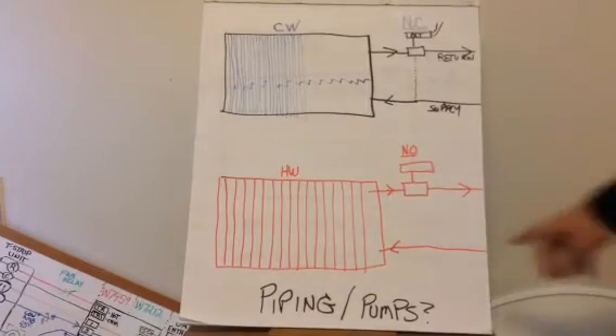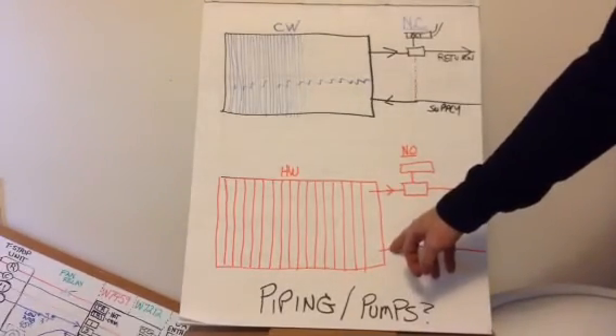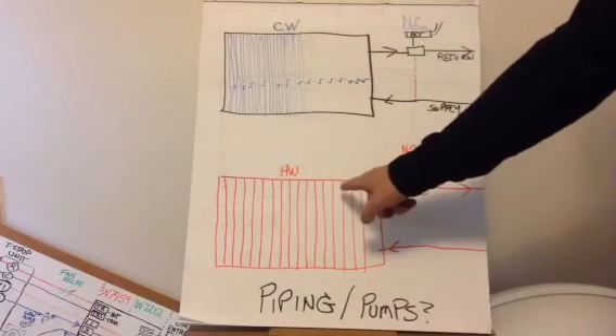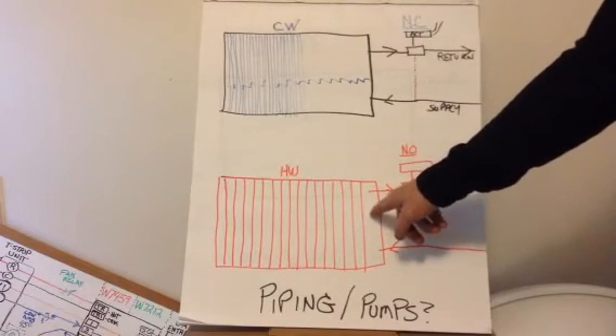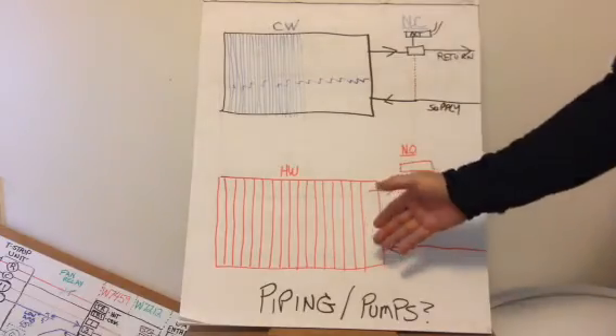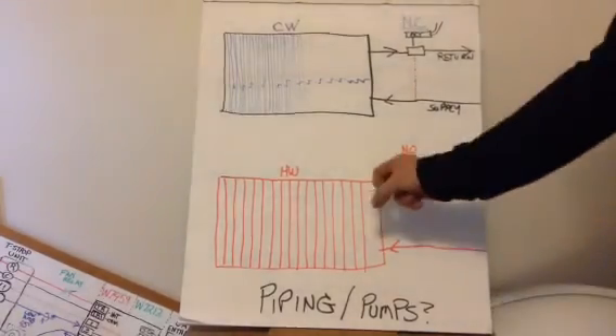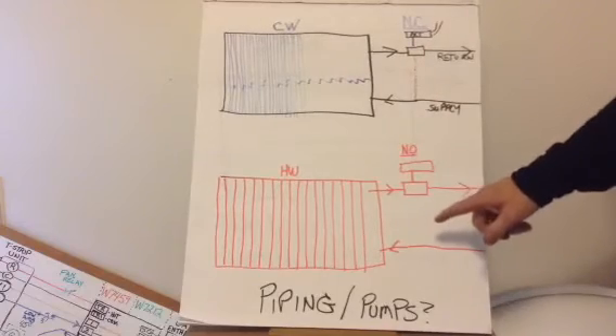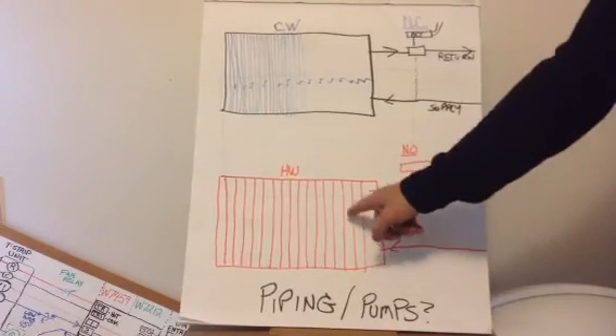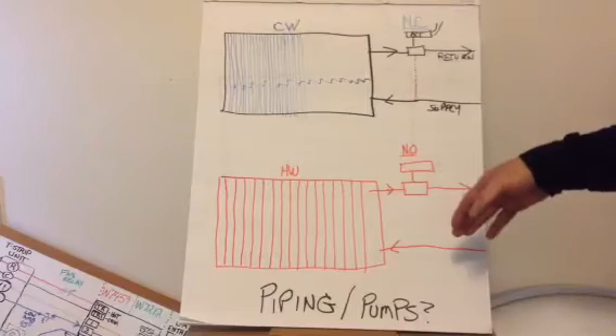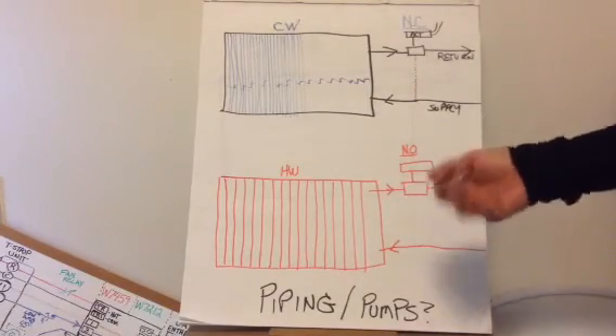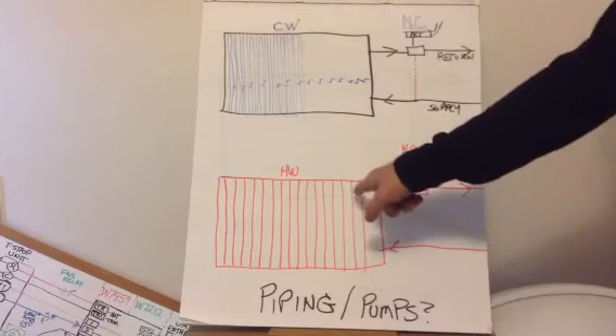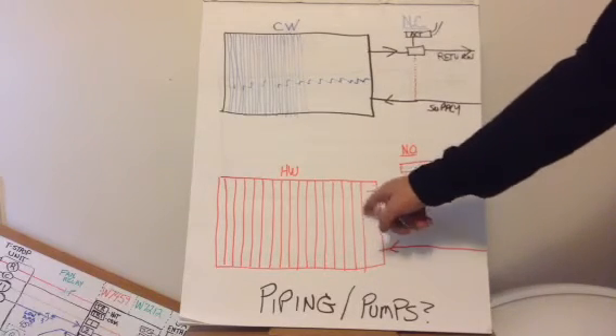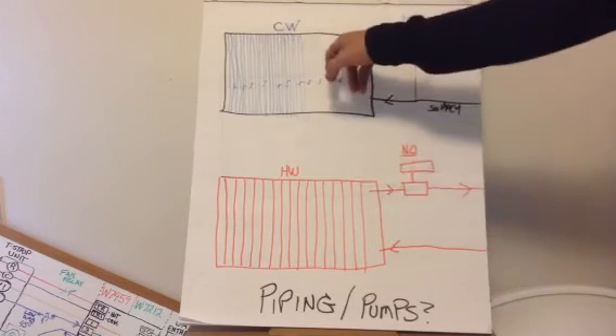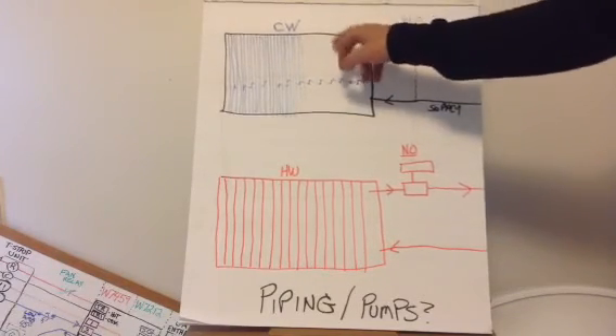So if you put chilled water in this coil, if someone pipes it backwards and you've got chilled water going into this coil, number one, you don't have as much contact time, so you won't cool as well. So if you have a cooling problem in a store that you've never been able to figure out, you could be piped backwards. You could have the chilled water going through the hot water coil. It's not designed for that. The other thing you have to pay attention to is because there's a bigger gap here, the air goes past this coil. This coil doesn't get dirty. So you might look in here and say, hey, these coils are clean, I don't need to wash them. All the dirt's going to be sitting packed onto this coil.